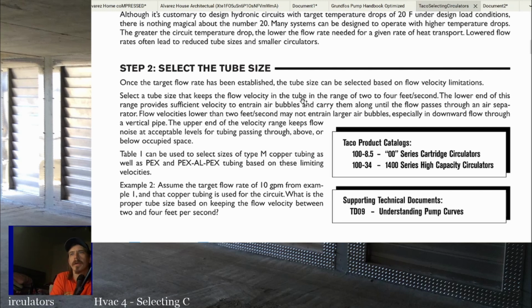And the other thing to keep in mind is, as the velocity goes up, if you try and size at a higher velocity, not only does the noise go up, but your pressure loss is going to increase. Think of it as it's moving faster, so you're going to have more friction in the pipe essentially. So generally, you don't want to figure more than about 4 feet per second inside the pipe, and we're going to talk more about that shortly.